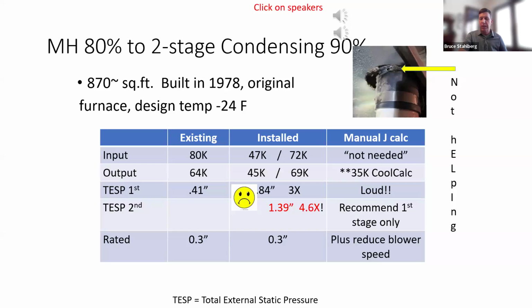So I called the contractor back. The furnace seemed to be very oversized, so we were running it on first stage only. That means you paid for a two-stage furnace, but we got one stage. And here's what the result was on the second part of it. So we're at a home where we installed a furnace and we had to come back and do some tweaking on it. Can you tell me any of the changes that you've noticed? Yeah, the furnace is much quieter. It doesn't get that loud noise that was waking me up. I've noticed that even with the rising cost of gas, my utility bills now are lower than they were last winter. So it's been working really good. Good, glad to hear it, thank you. So I feel much better about leaving the job. It's nice to have heat, but we shouldn't be waking people up as a trade-off for that.